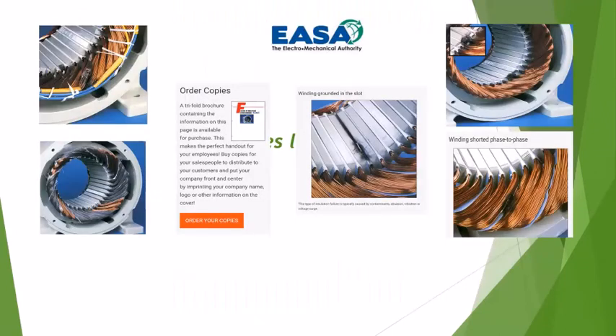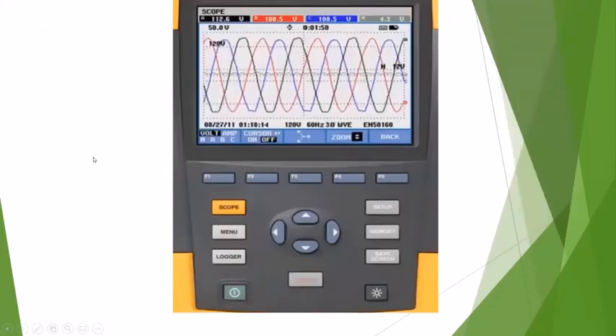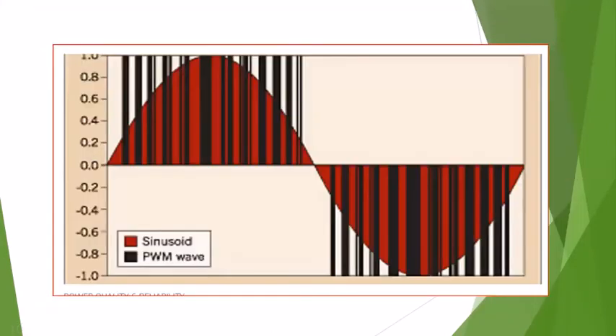Let's see. I also do have available, if you would like, send me an email or whatever. But it's important also to understand what causes motor failure. And so this has been a nice chart that I found. This shows, if it was a spike in power, this shows if it ended up being single phased. This shows, typically this happened if it's been dragging, burns insulation and then shorts here. But it kind of gives a simple tool to pinpoint where the motor problems are coming from if they do show up.